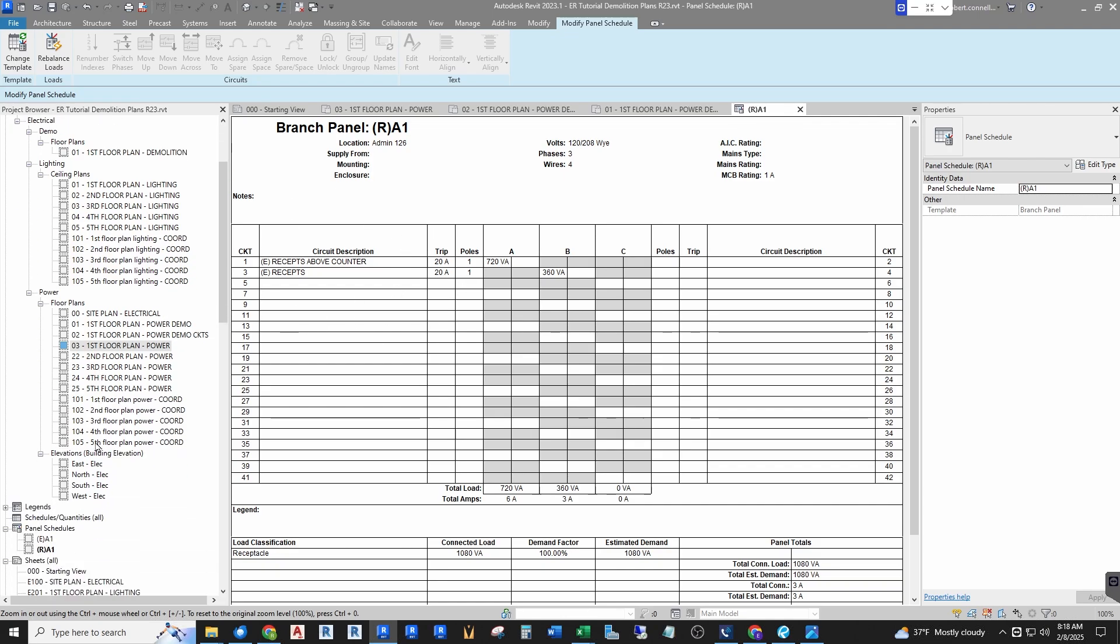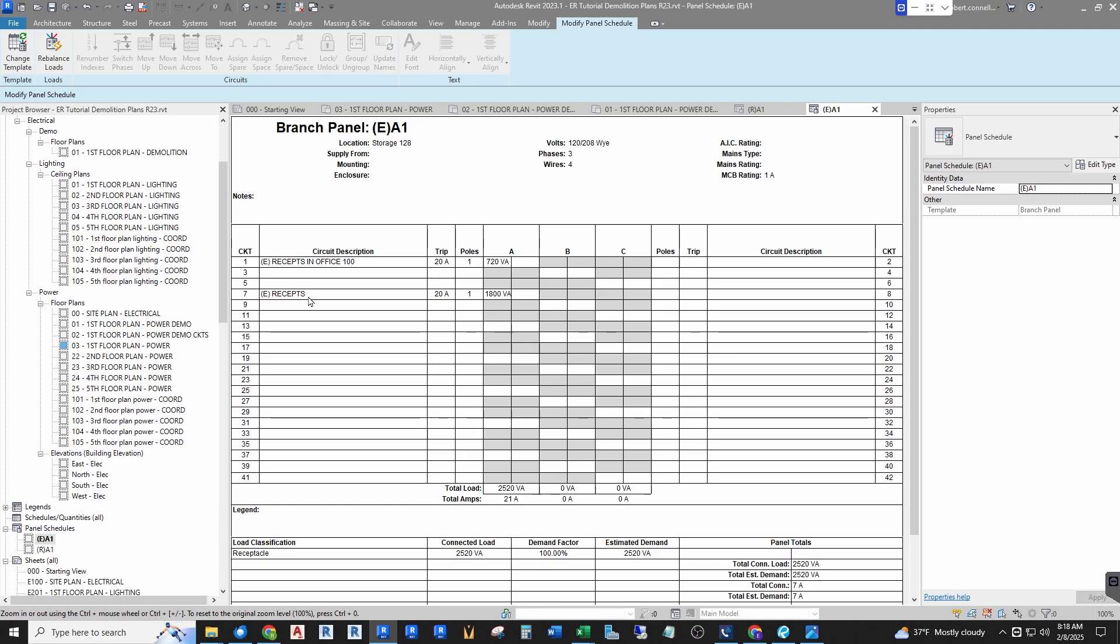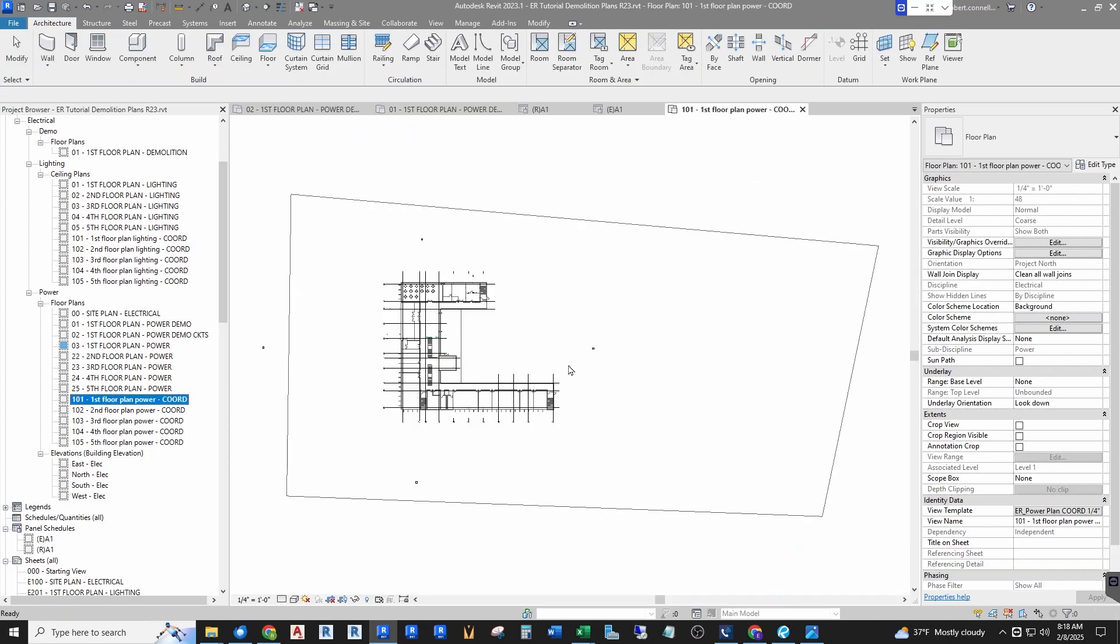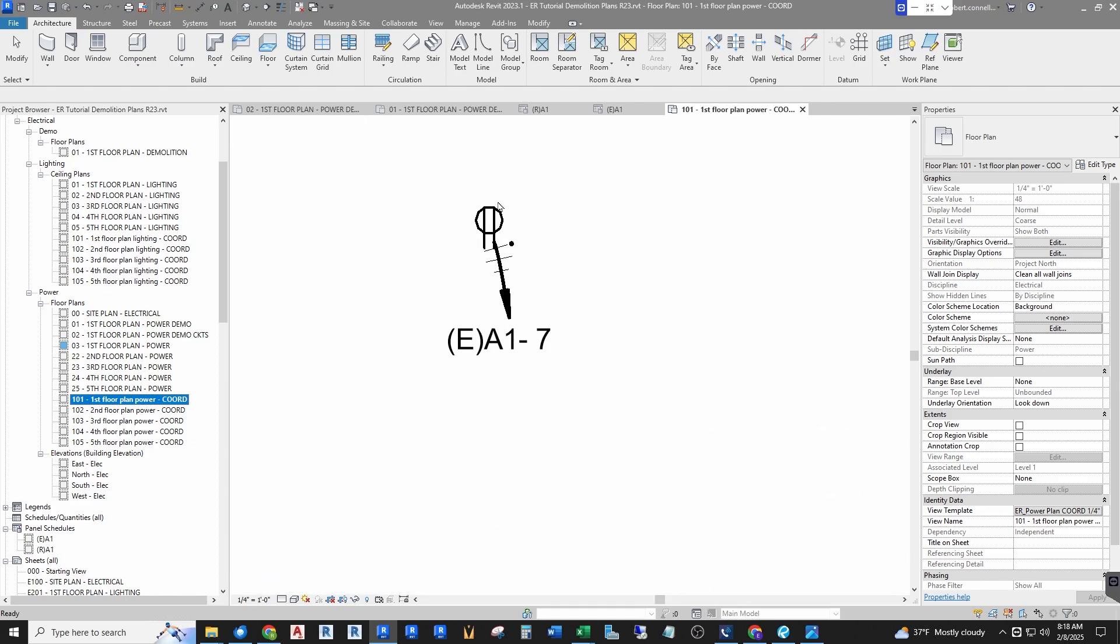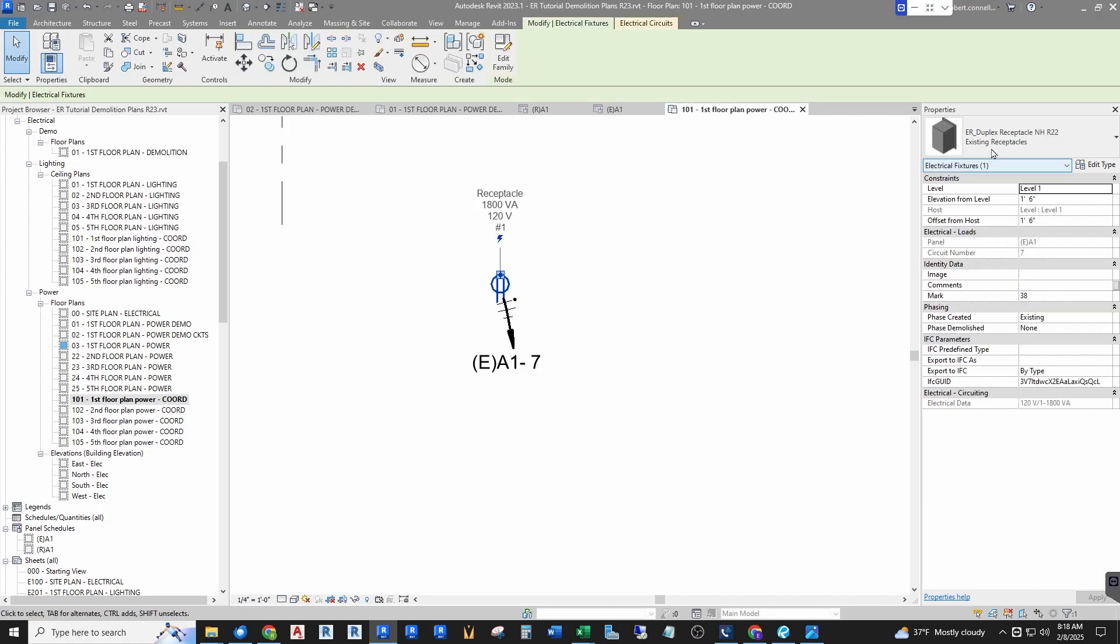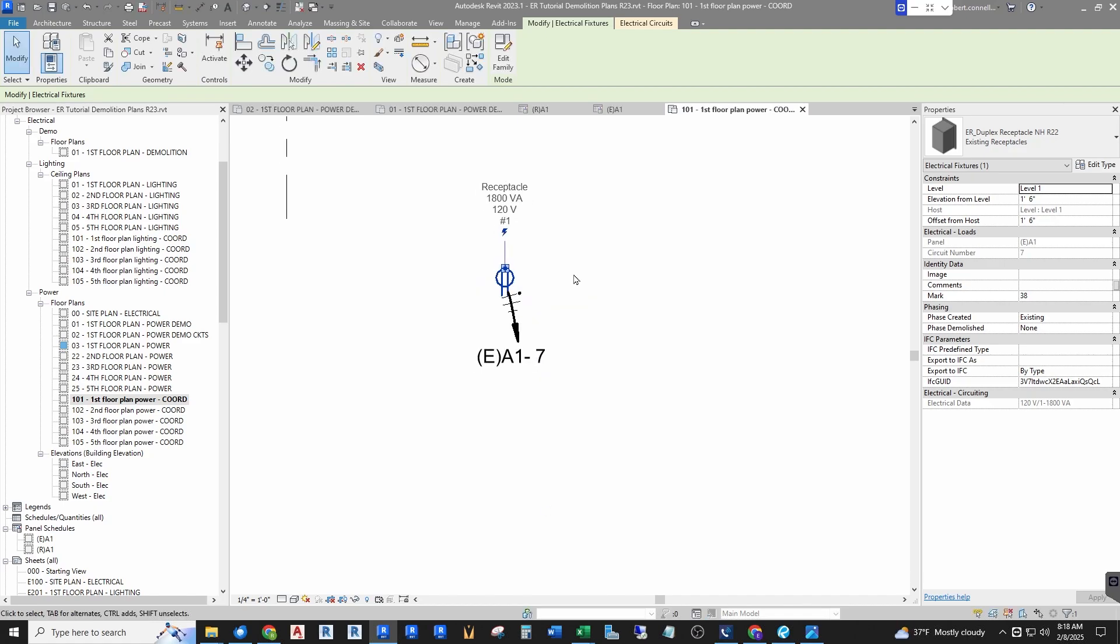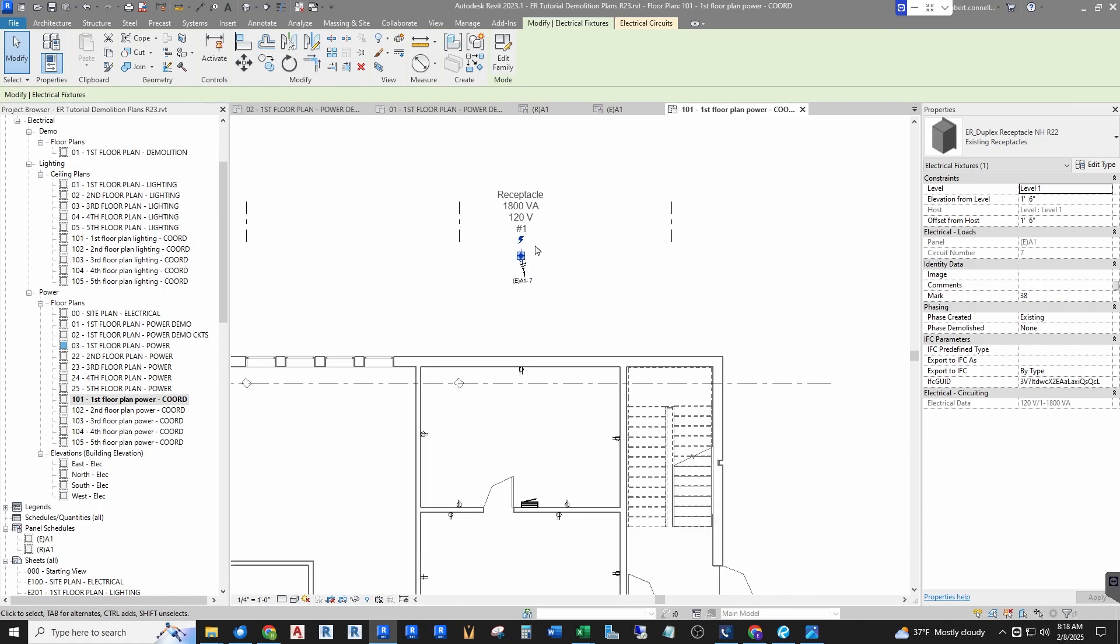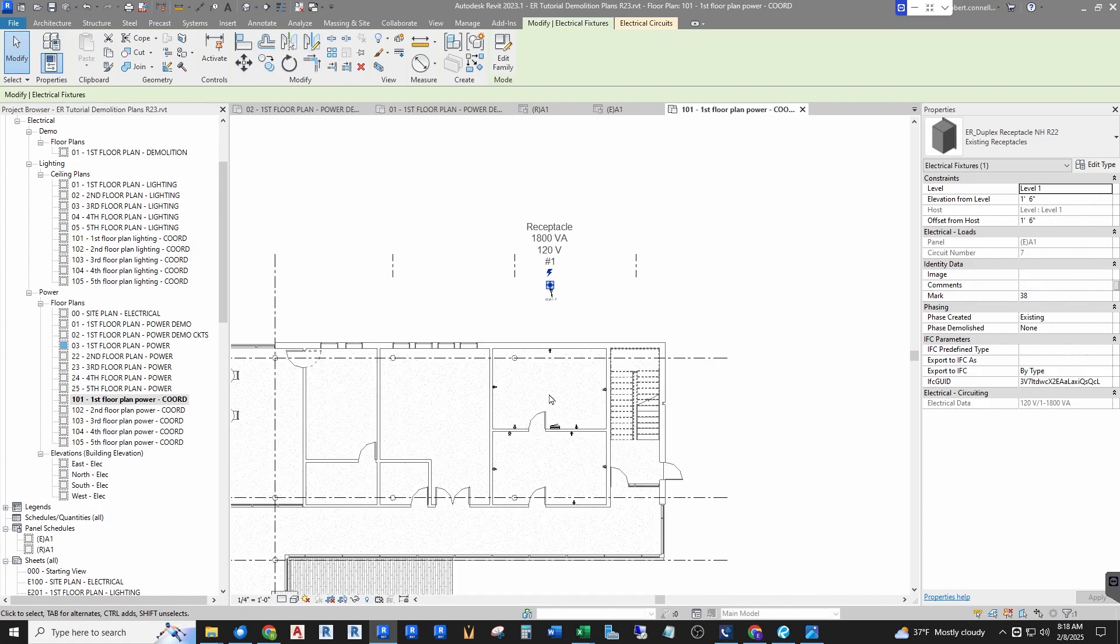Now the old panel, the removed panel, does have some other circuits in it that are being demoed. Now one circuit I didn't show you that I also showed on a previous video of how to show existing circuits even if you don't have them in your plan view. For example, let me go to my first floor plan coordination view which doesn't have any cropping, and you will see out here outside the building I have an existing receptacle that I just called existing receptacles and it has a load of 1800 VA on it. Again I have a link in the description below on how I deal with existing circuits that may not be actually shown in the plan.